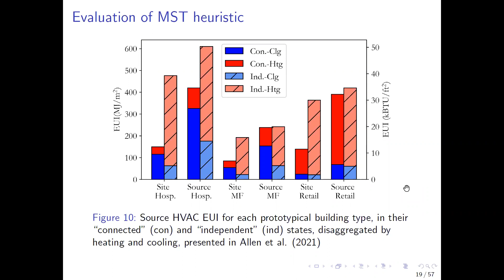But the most significant reduction was observed for the prototypical hospital building, primarily due to its high levels of internal load diversity, in which the water source heat pumps serving its zones operated somewhat analogously to the 5G DHC loop as a whole, allowing loads from zones in opposite modes to offset each other. This has been observed in past work as well.